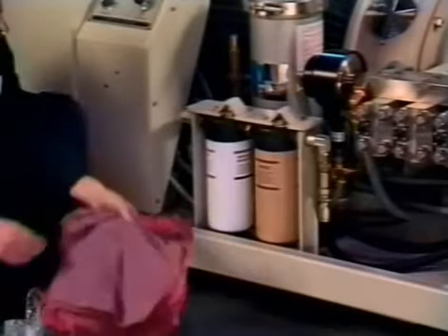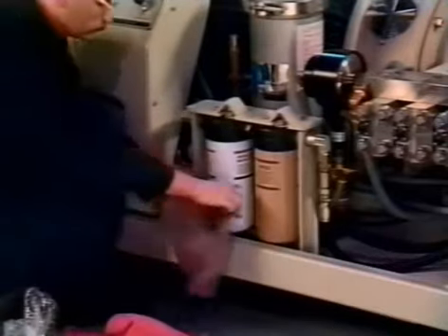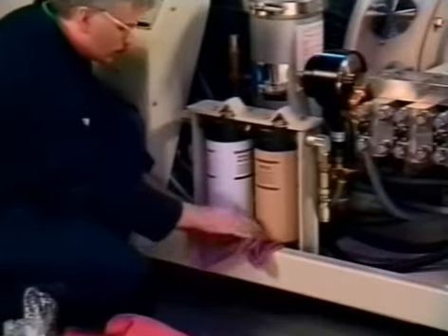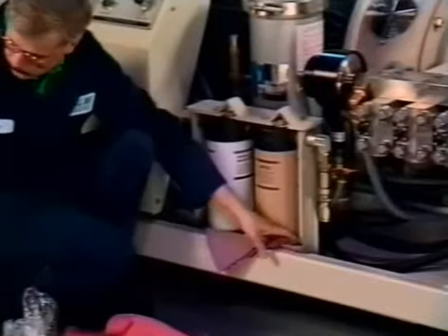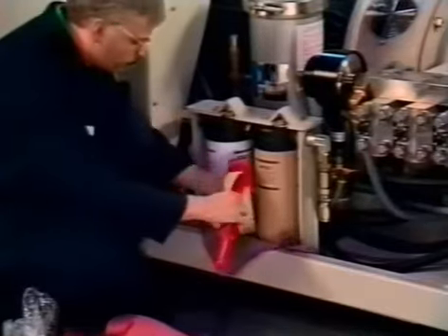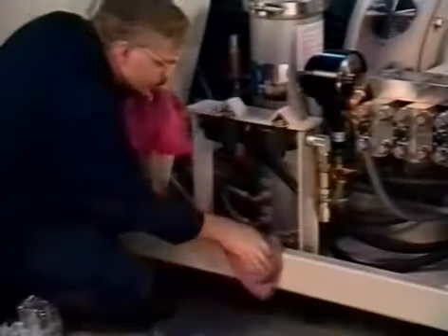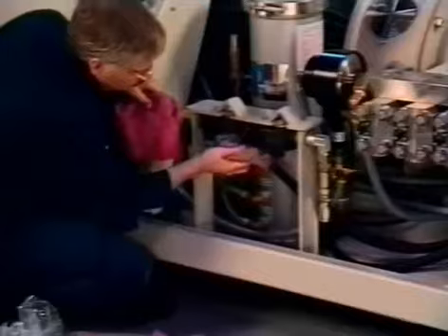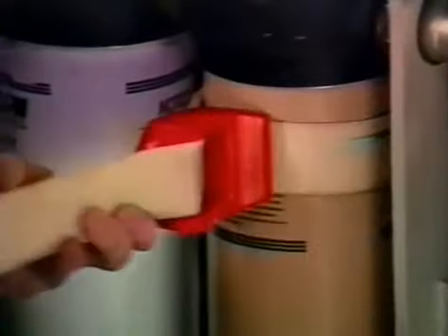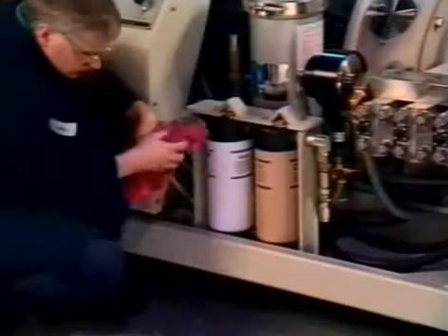First, remove the filters with a strap wrench. Then wipe the filter head and O-rings. Install the new filters, tightening them with a strap wrench. Failure to change the elements will cause damage to the internal components of the lubrication system.